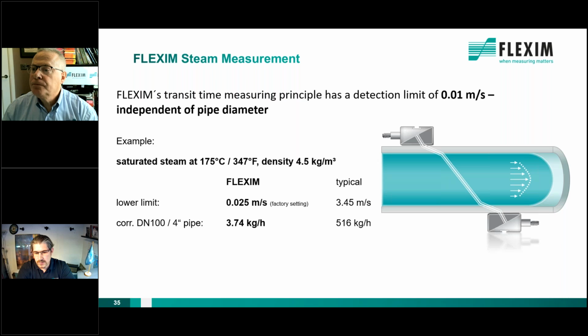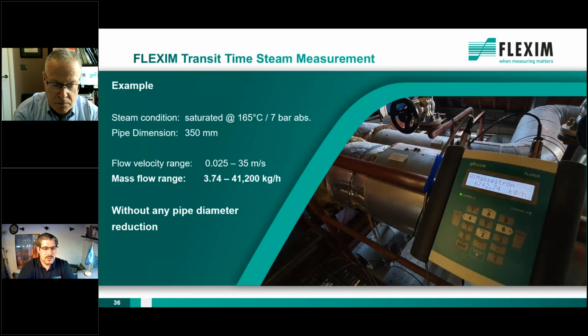Against this, we have a conventional meter, for example, a vortex meter, which would start measuring only at 3.45 meters per second. So the minimum flow that you are able to see is 516 kilograms per hour, so much higher. So what does it mean? It's not necessarily a leakage meter or a low flow meter. It just means that you have this whole flow range available, 0.025 to 35 meters per second, without the pipe diameter reduction.